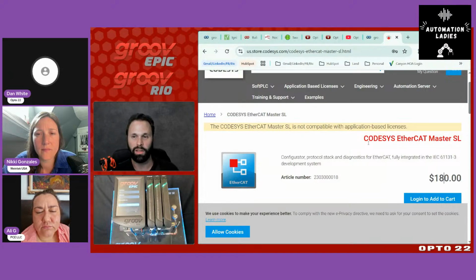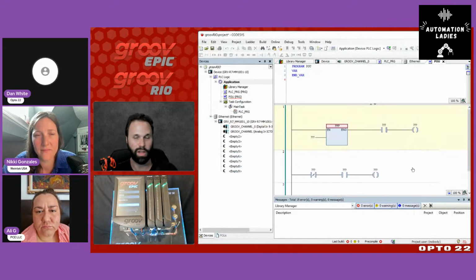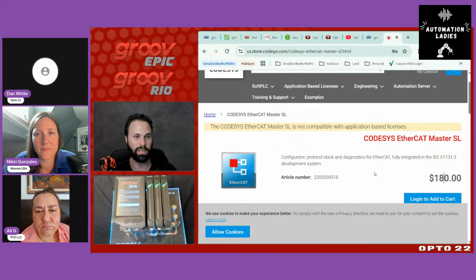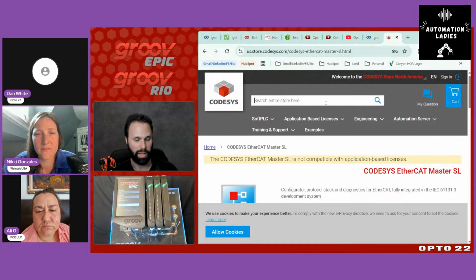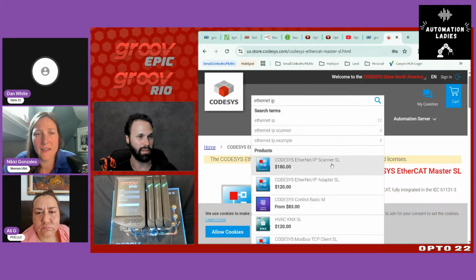Let me be clear: the software license for CodeSys is free, so you can run CodeSys on the EPIC with the license included. But when you want to add drivers, you need to look into their store - you can see Ethernet IP scanner and master options there. Scanner is their word for master, and adapter is like a slave, using the old master-slave lingo, if that's still allowed.